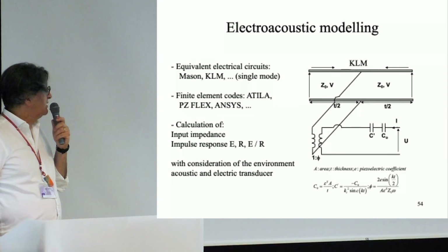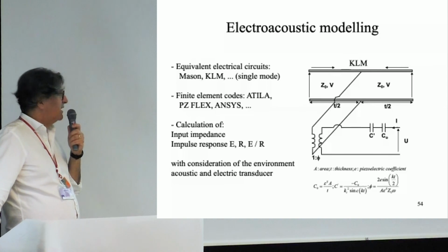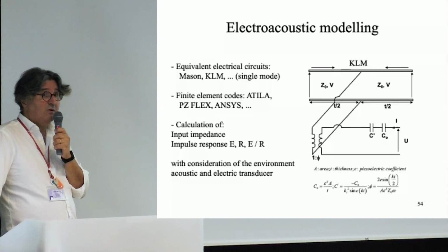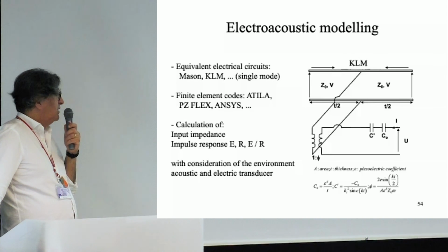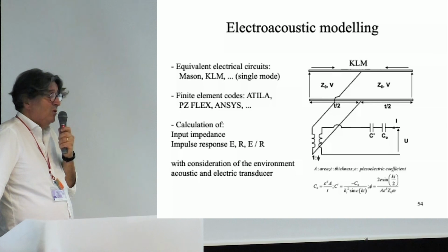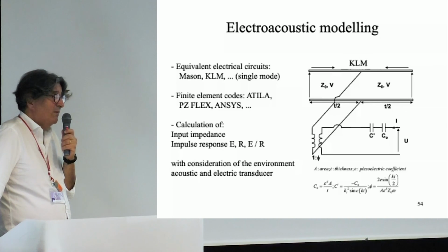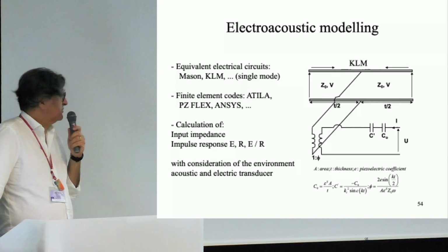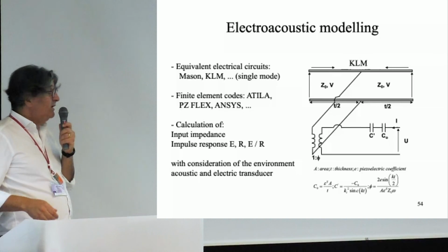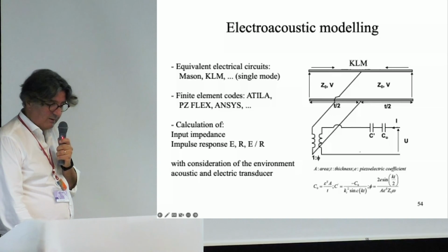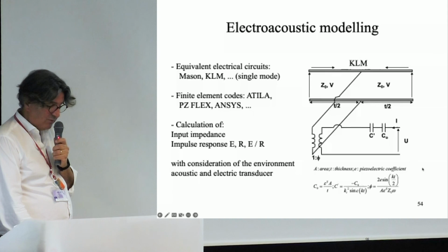So you have Atila codes, you have PZFlex, ANSYS, and so on. You have COMSOL that you can use also. And these models will allow us to determine all the characteristics of the transducer, even including the consideration of the electrical environment, of course.